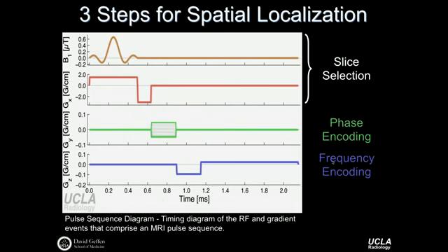These gradients allow us to form the echo, the gradient echo, for example. This is a gradient echo sequence that's shown. But at the same time we're forming the echo, we're also getting some spatial frequency information. And it's during this plateau, and I should have drawn it actually as the fifth axis here, but it's from this point here, you can see this gradient's on just a little bit, right? It has a relatively low amplitude, and it's turned on in this case for about a millisecond.